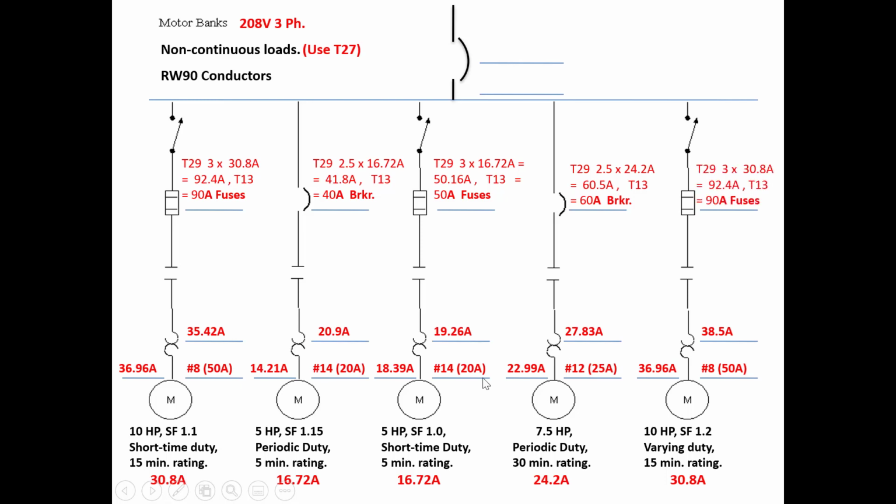So if you want to double check when you're going through it, all these ampacities before we pick the wire size are based on timesing the FLAs from table 44 times the percentages found in table 27 because we are non-continuous.